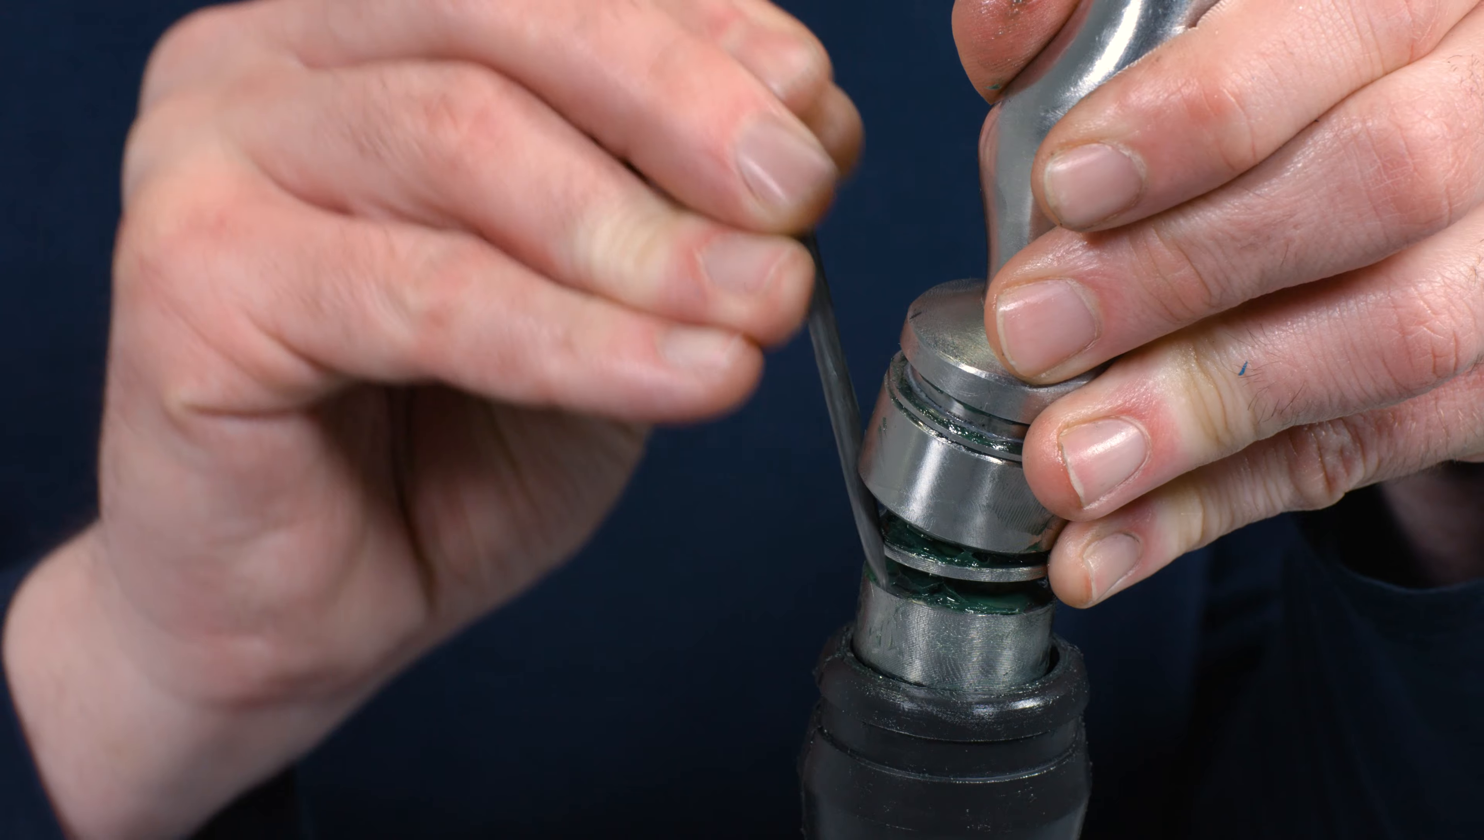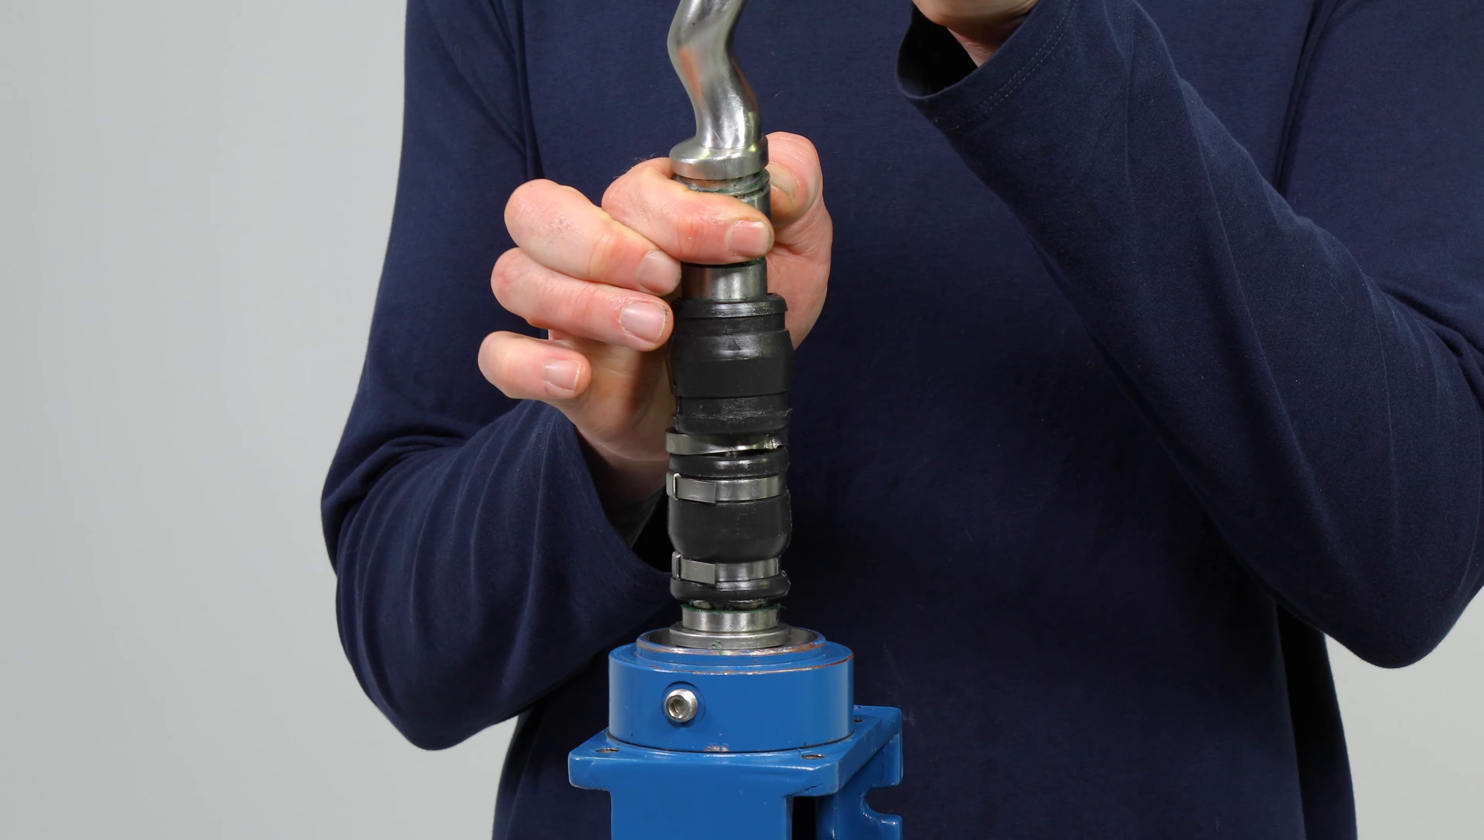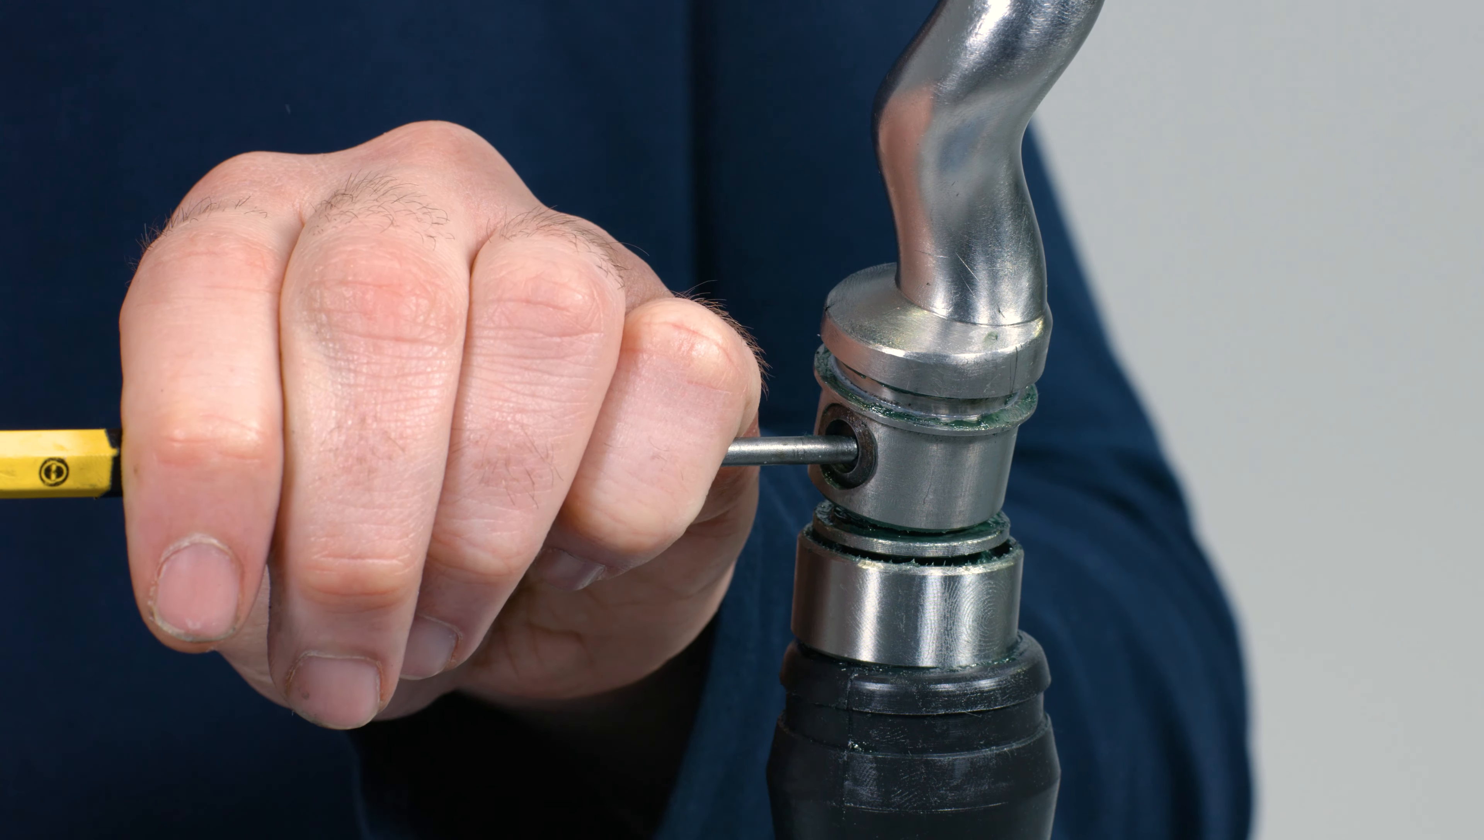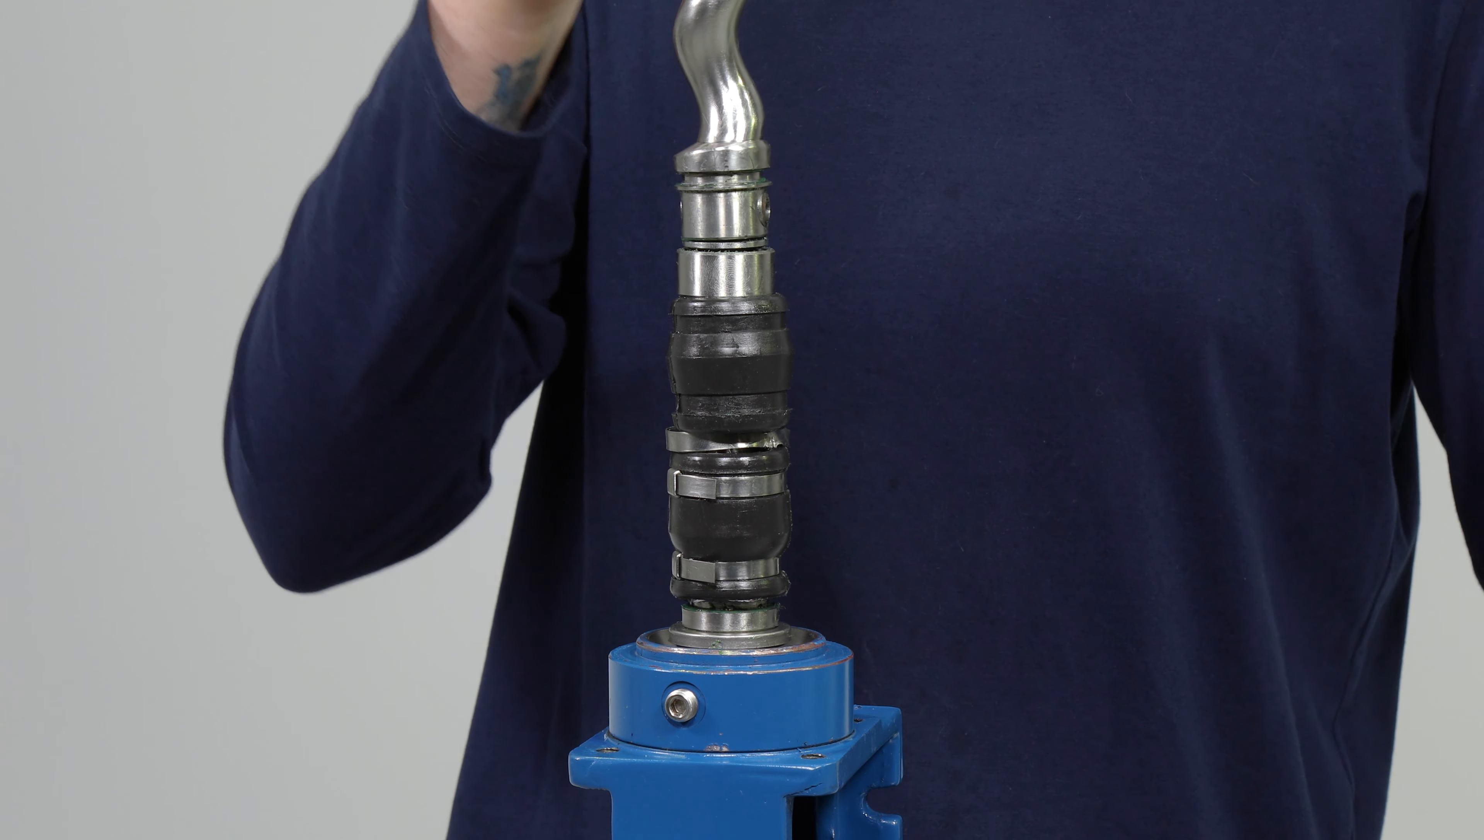Use a small file to remove the peen mark used to keep the pin cover sleeve on the rotor head. Slide the pin cover sleeve down and off the rotor head. Remove the pin by using a punch and hammer. Once the pin is removed, you can lift the rotor off the connecting rod.